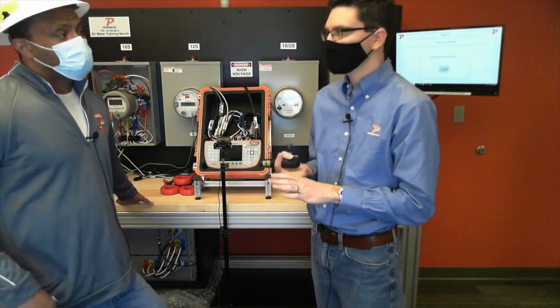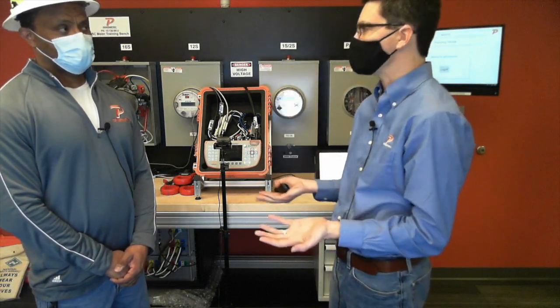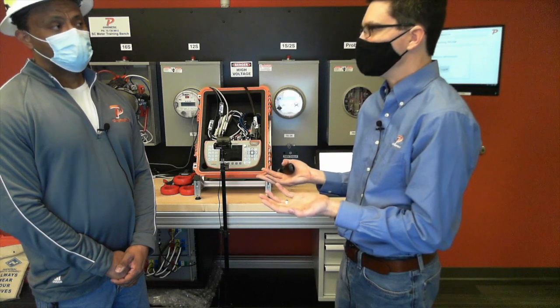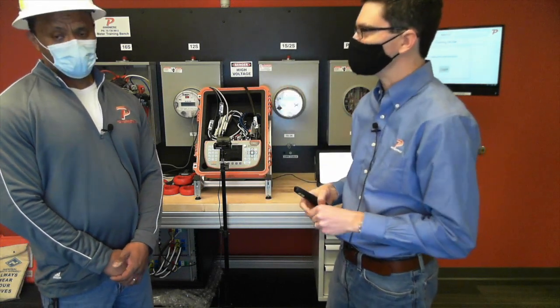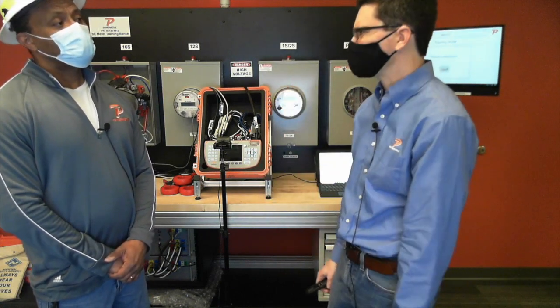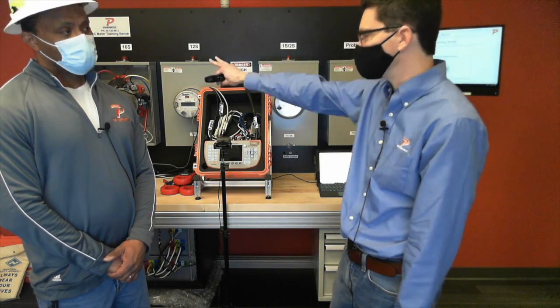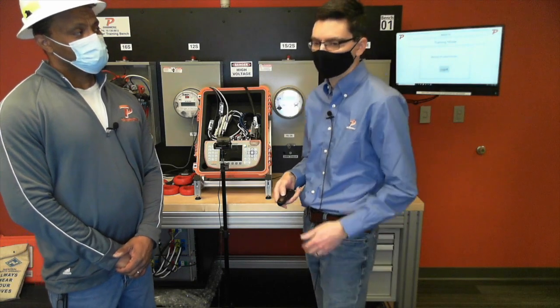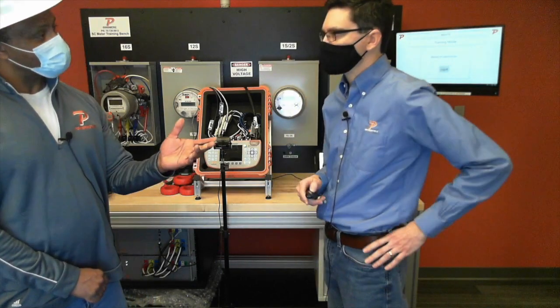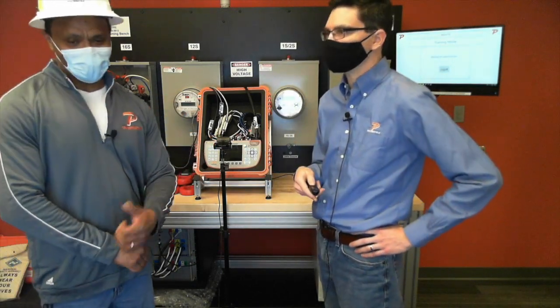That's fine, but we like to recommend doing a customer load test, because if you have a customer complaint, they're going to want to see it in the socket. They'll say, I don't know what your magic box does when I plug it in there, I want to see it here in my socket. Exactly, this is why we advocate this method. Then you can tell the customer to go turn something on so you can measure it, like turn your AC on.